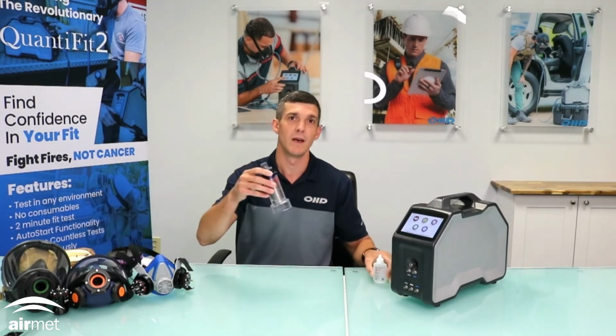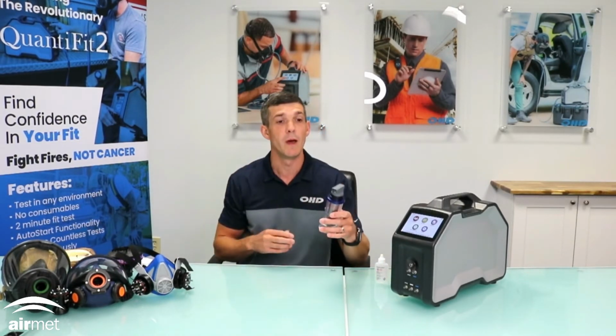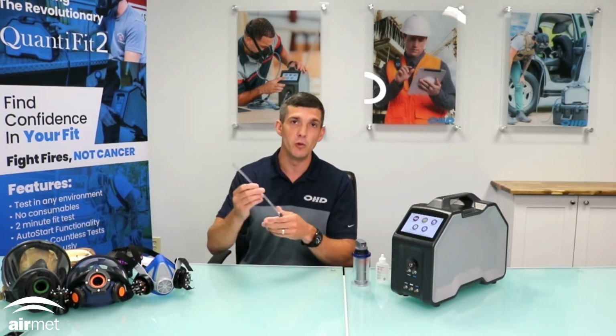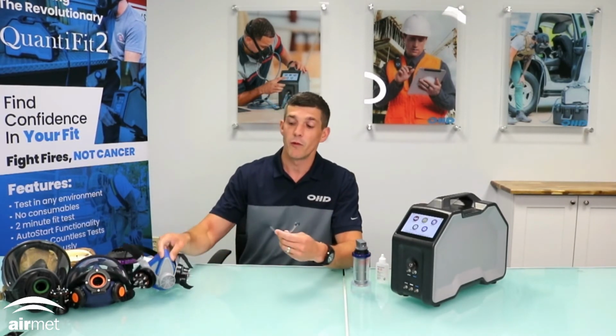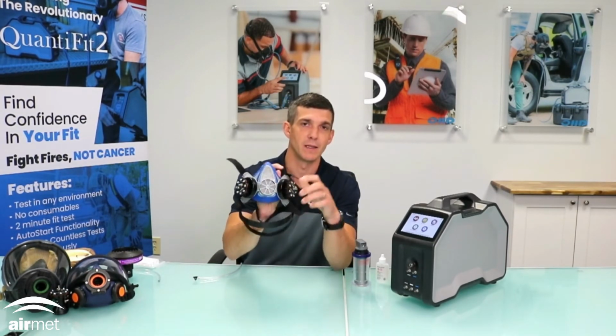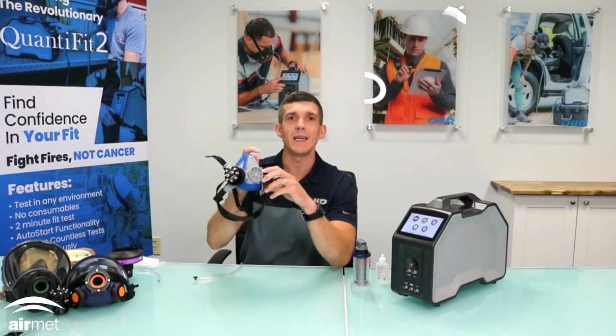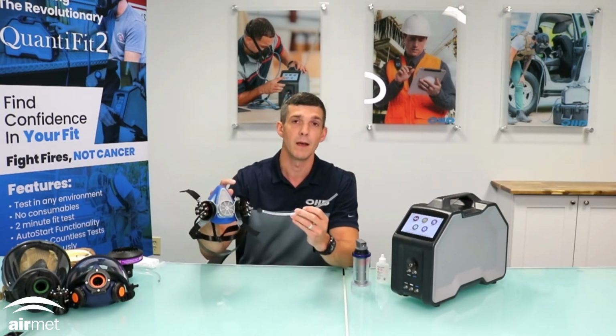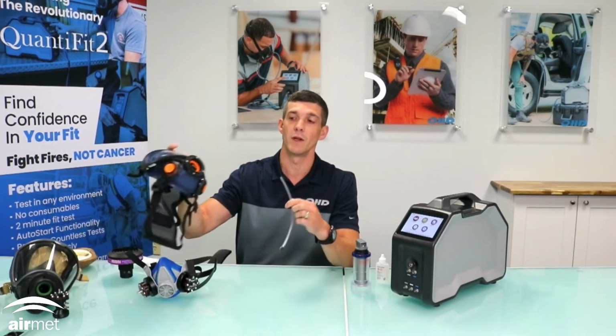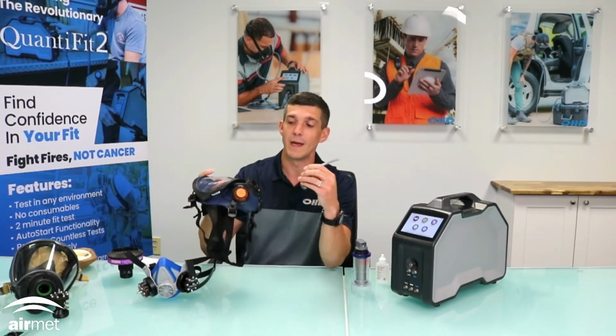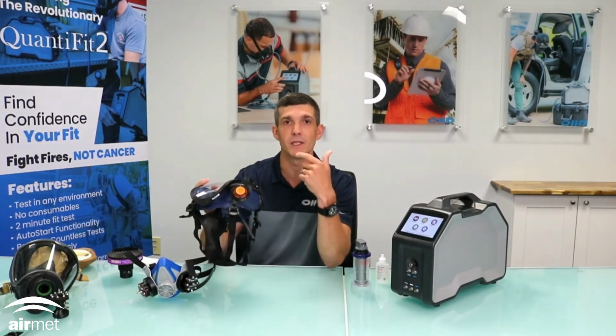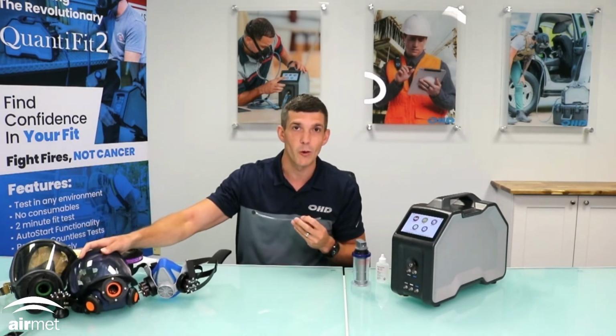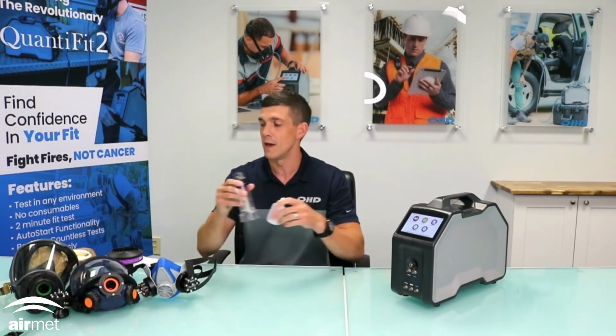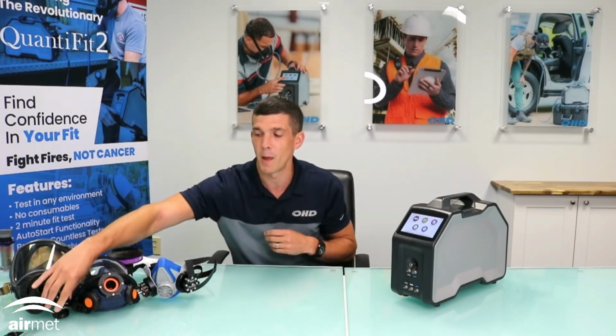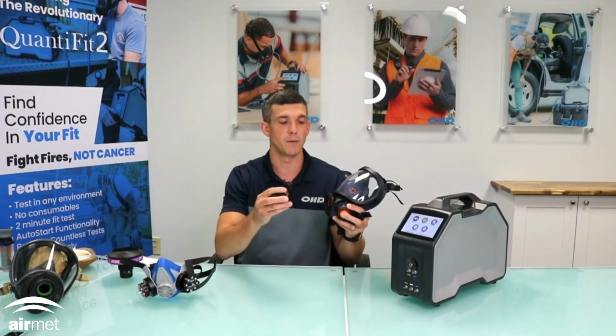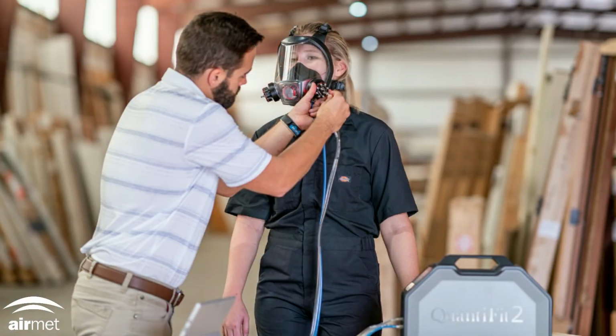You do not have to have wicks that have to be saturated inside of a tube and then put into the instrument. You do not have to have probes that have to be run inside of a facepiece. So with controlled negative pressure, our adapters just connect to the side of the respirator. In some masks, it is easy to probe a respirator with aerosol type testing, but in some respirators, it's extremely difficult to run the oral nasal probe into this passageway in the mouth and nose area, every single respirator every single time. The beautiful thing about controlled negative pressure is we remove all of these requirements that go into doing testing with other technologies, and we use simple adapters that connect directly up to your respirator, right where the filter would be connected, and you're ready to test.